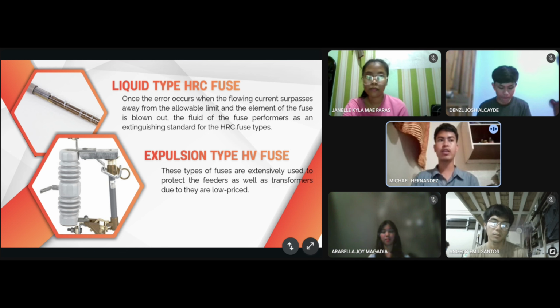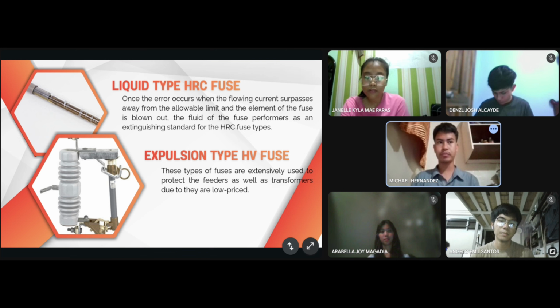Inside the fuse, there is a special fiber tube and fuse link. When a fault occurs, the fuse element heats up and melts, breaking the circuit. At the same time, the heat causes gases to form inside the tube, which are then expelled at high speed through small vents. These gases blow out and help quench the arc, stopping the current flow almost instantly.